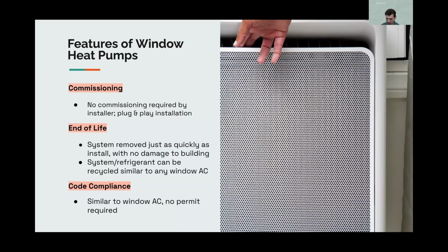On commissioning: when we started on this journey, we talked to a lot of customers about the performance of their systems. What we found, which in hindsight isn't surprising but was surprising at the time, is that nameplate efficiency is not what's driving a lot of existing energy use. A lot of it comes down to how systems are designed, installed, and used. The human interaction and the installer and maintenance interaction with actual energy use are huge. The advantage of a fully packaged system with minimal on-site configuration is that you don't need to worry about duct balancing, sizing the right air filter, or other human factors. You really ensure the quality of the install is consistent and as designed.